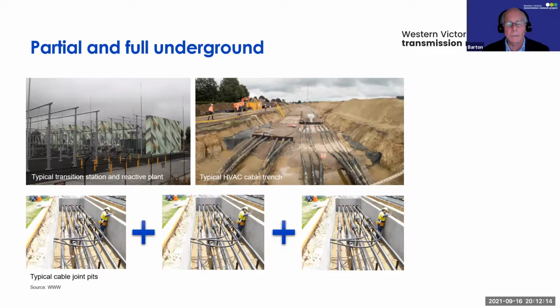So if you wanted to, for example, cut into a HVDC circuit at say Ballarat North or Waubra or wherever, you have to put what we call back-to-back converter stations—one to bring it from DC back to AC, then you make your connection at AC because that's what all of the rest of the network operates at, and then you transform it back to HVDC. So every time you want to cut into a HVDC line, which is typically not done, you incur a cost of something like 10 or more times to do the equivalent cut-in for a HVAC.